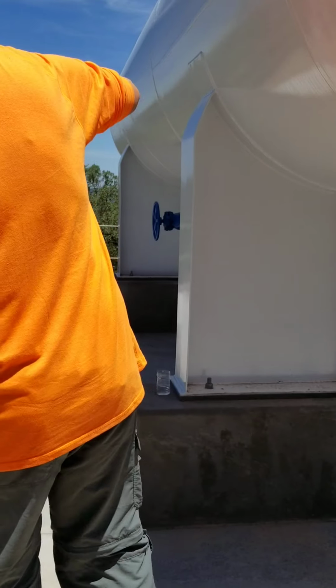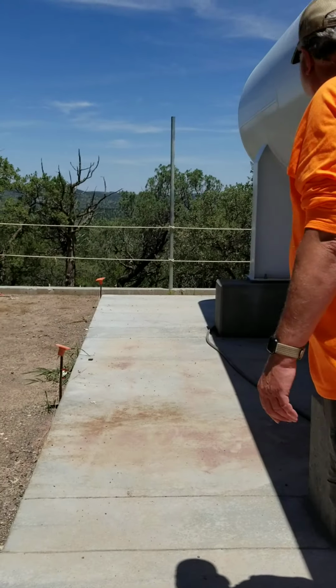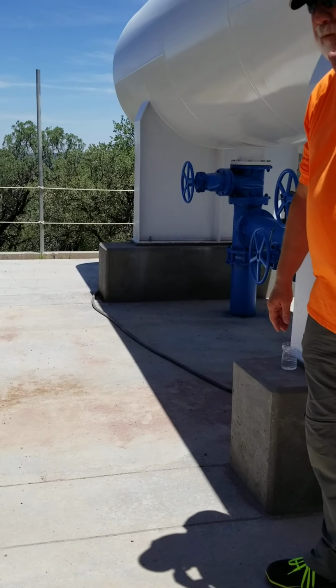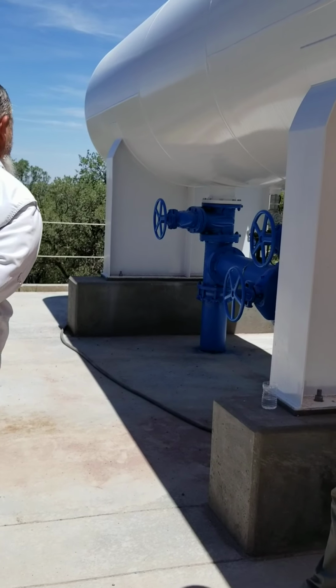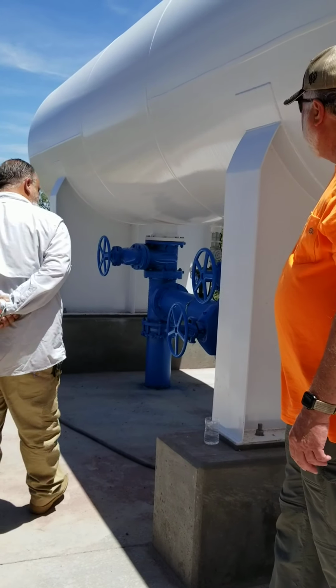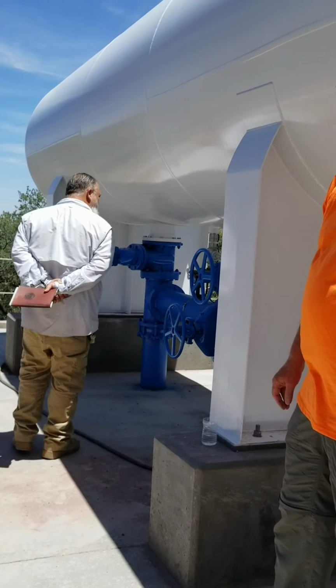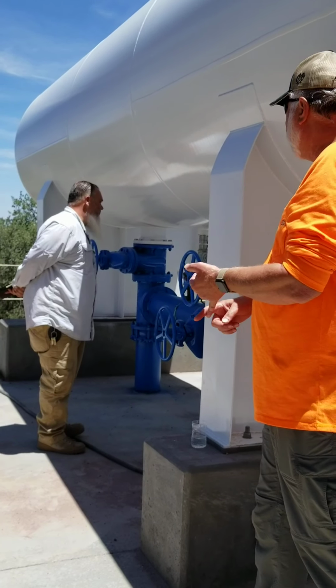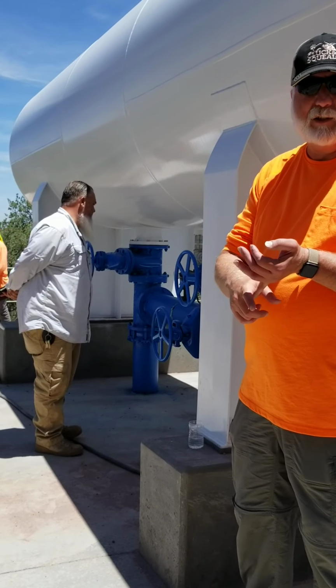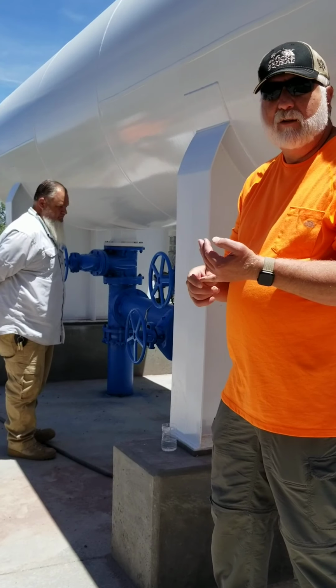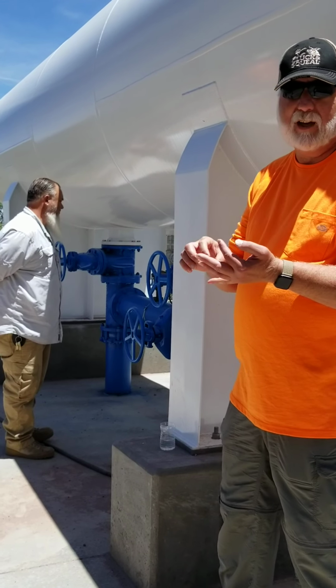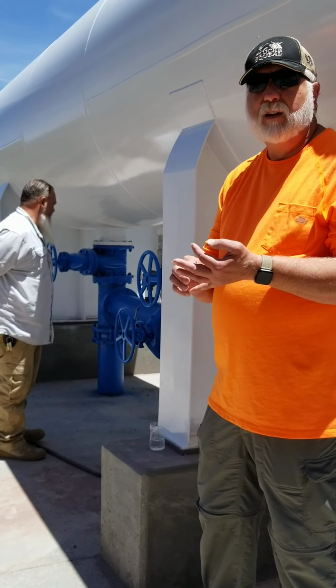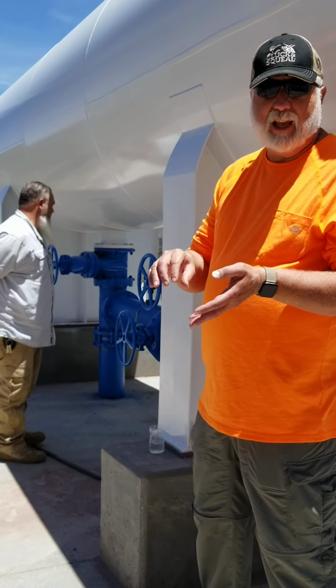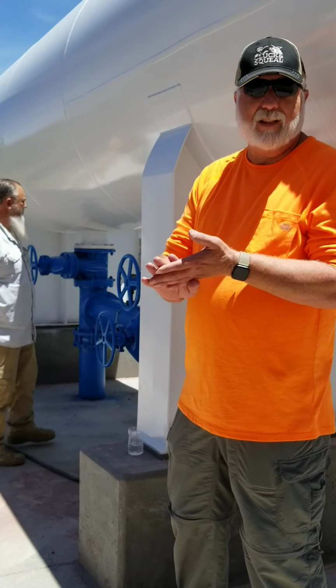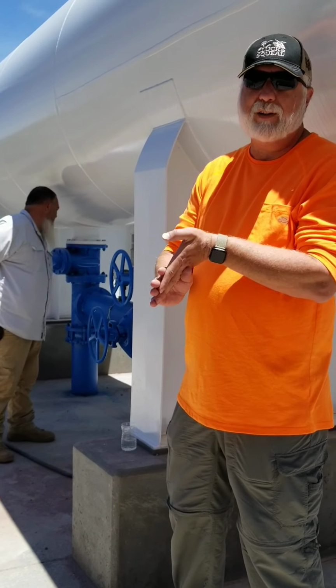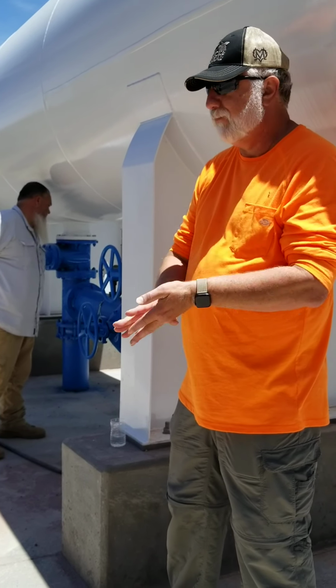On the other end of the tank, you have a manway. That's your access in and out of the tank. By most codes, it's required to take the tank out of service every 5 years. Go inside. You can lightly pressure wash it. Main thing is doing an inspection of the interior coatings. Make sure there's no cracks, flaking off of it. If there is any, get it repaired. If you do that, this tank will last forever, because the only reason they fail is from corrosion.